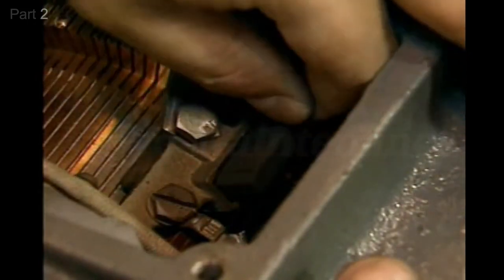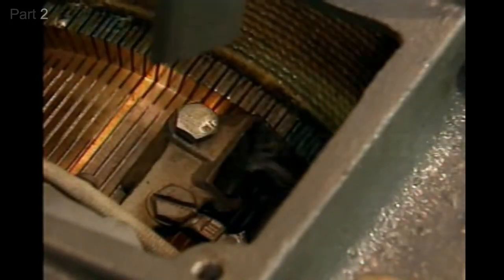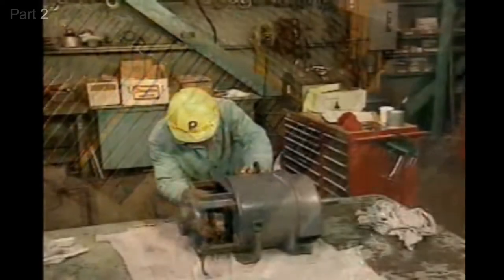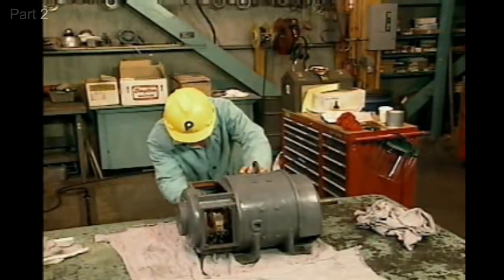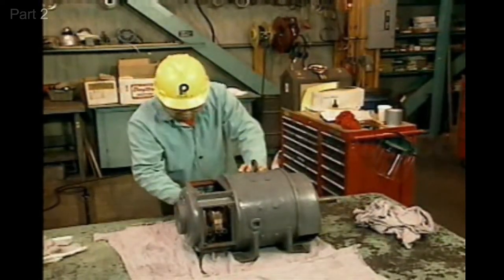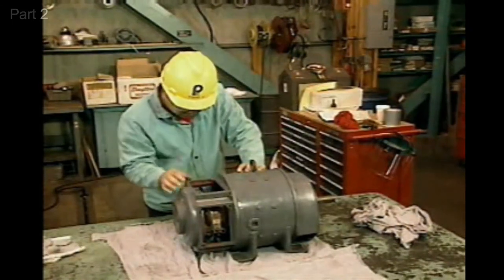The bottom edges of the brush holders should also be smooth, straight, and free of burrs. If they're not, the edges must be smoothed with a file or sandpaper or the brush holders must be replaced.